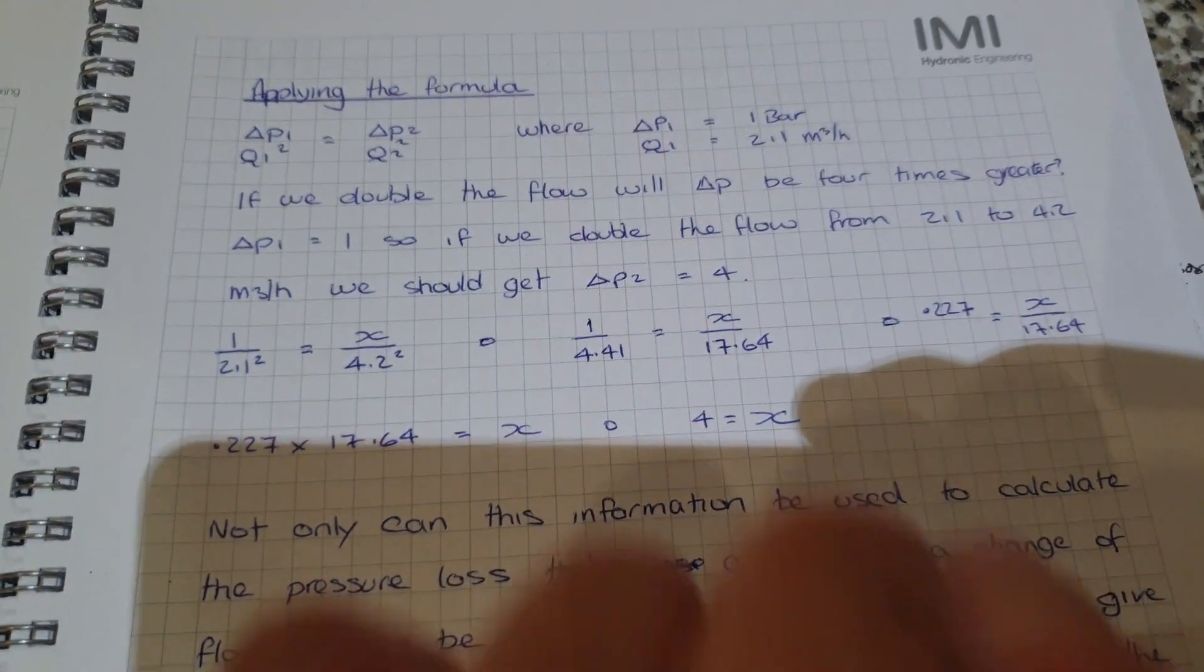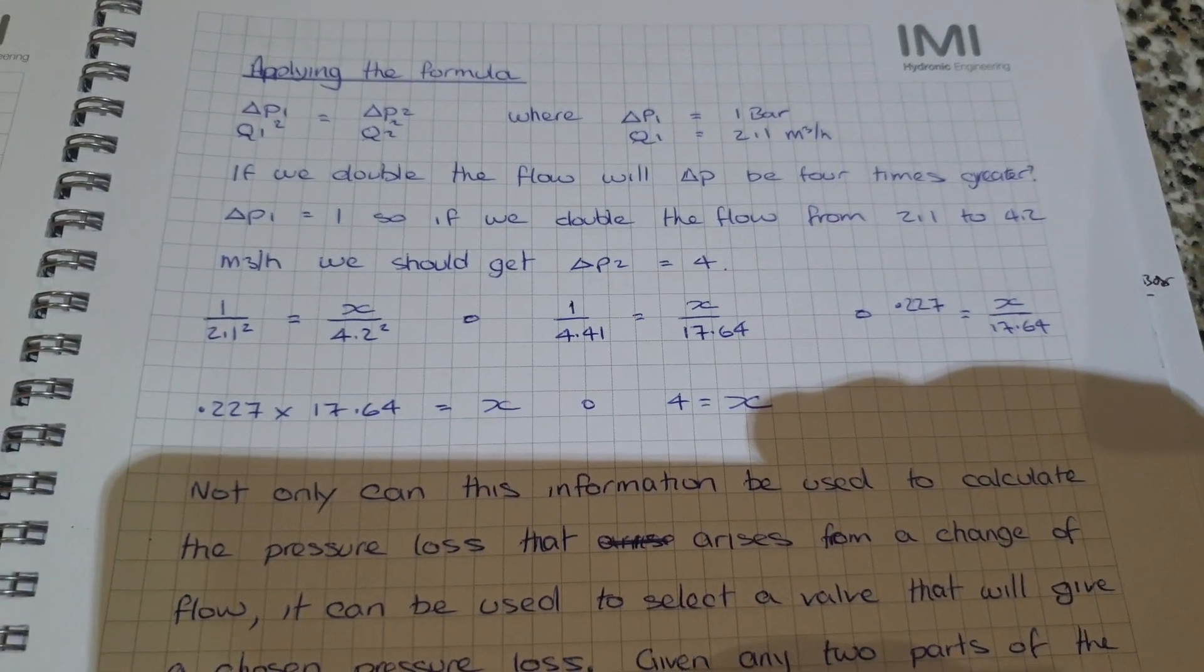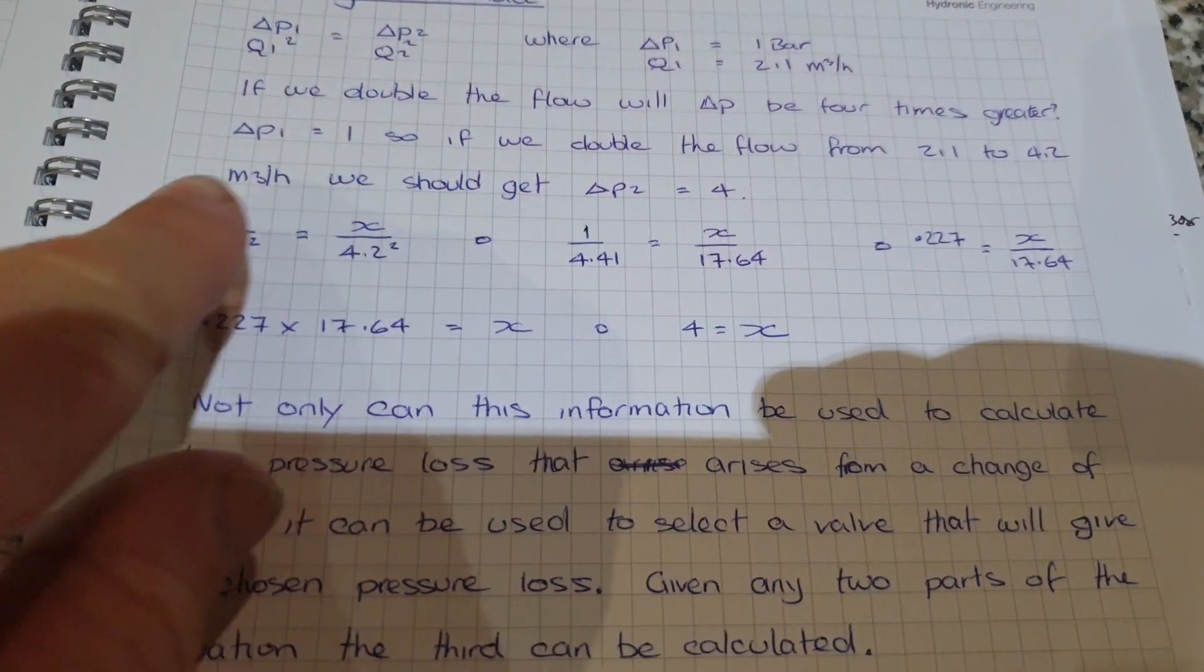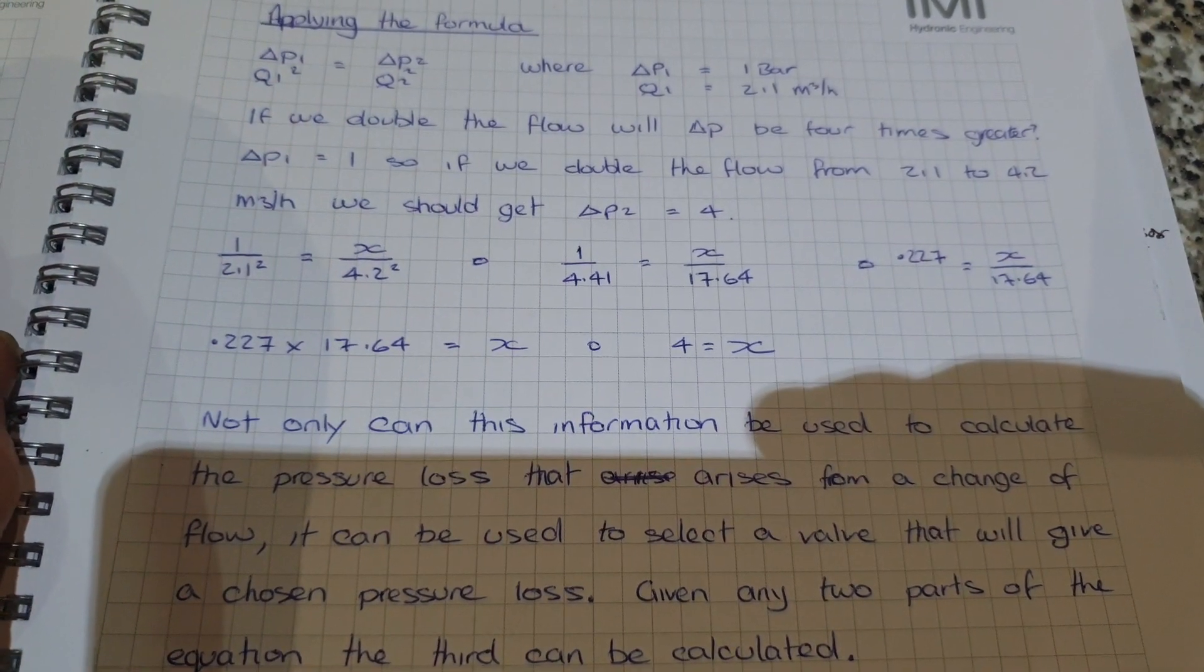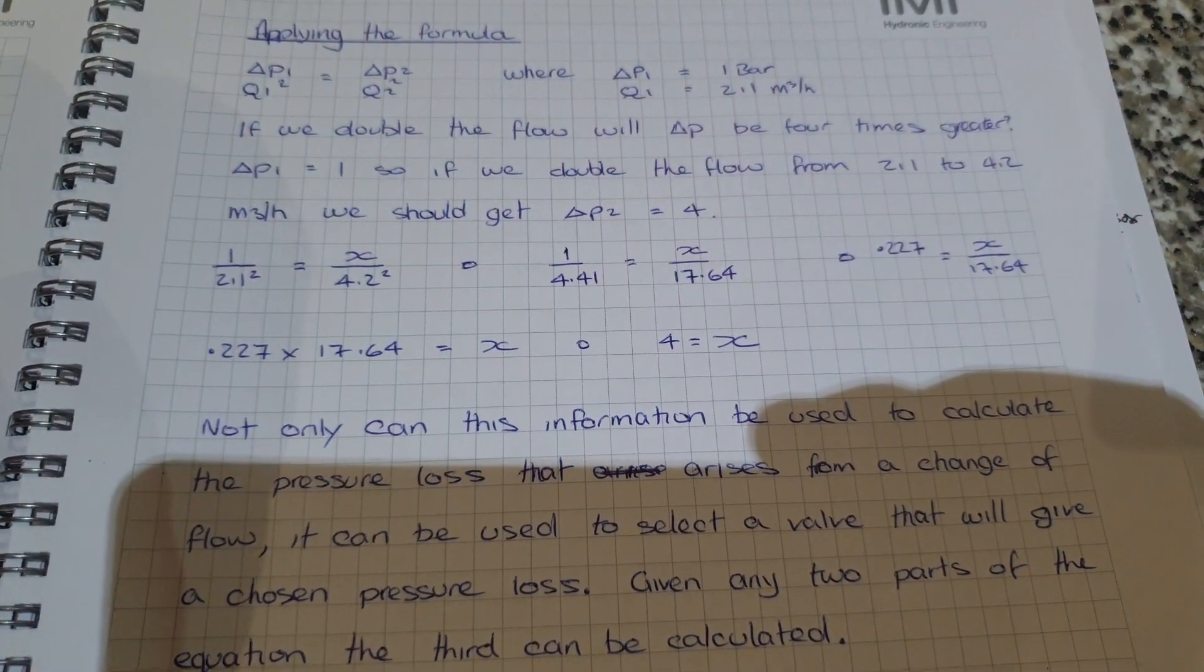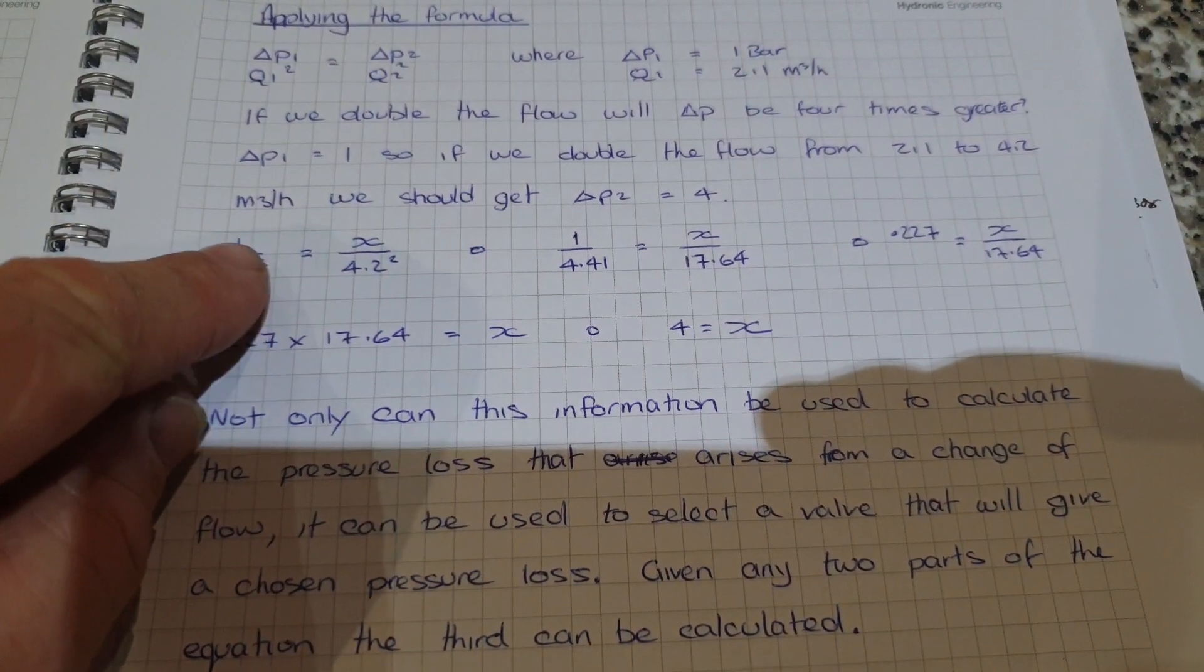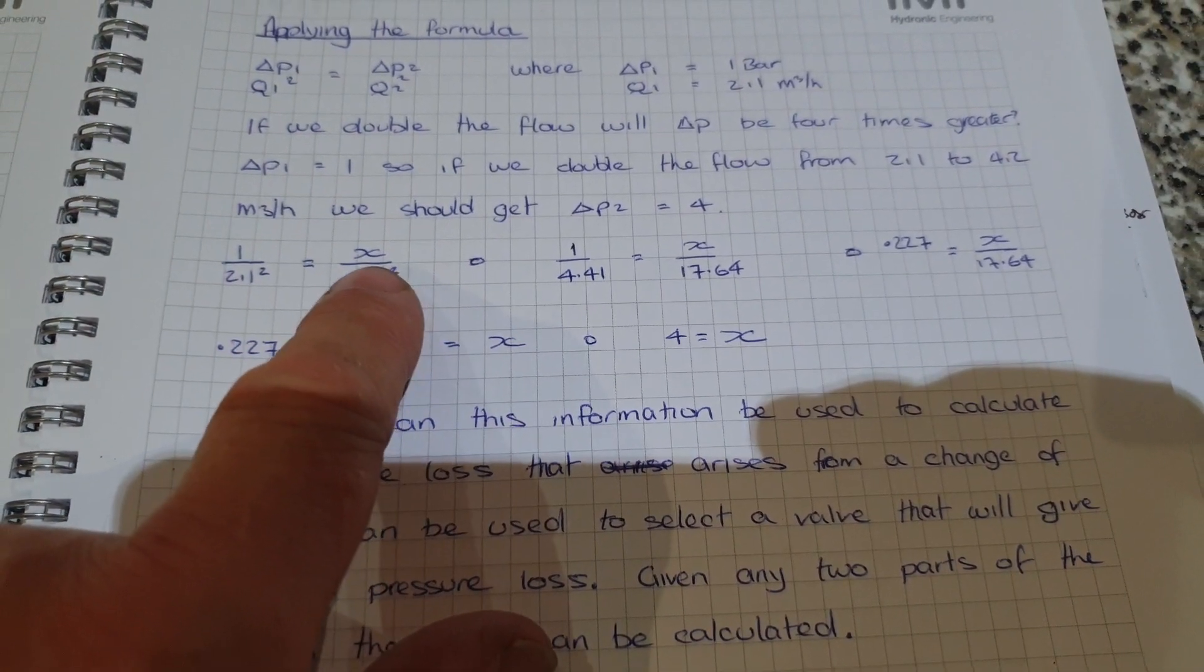We can test the formula. If this formula will do what we say it'll do, and we know that if we double the flow the delta P will be four times greater, then we can apply the formula to test that out. We've got a valve with a KVS or KV value of 2.1. Our delta P1 is one bar, which is what we've used for the standard. Our flow rate is 2.1 cubic meters per hour, which gives us the KV or KVS value.